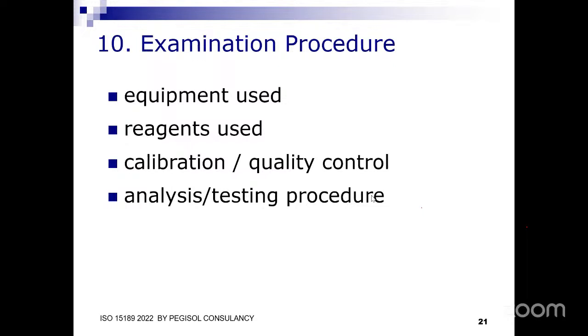So some people normally go for the unassayed QC because it's a little bit cheaper than the assayed QC. But whatever it is, if you look at the cost of everything, you have to run some samples before you determine the range of that QC. So that is also part of the cost you should look at. So that's the difference between assayed QC and unassayed QC. The assayed QC has a defined range, while for the unassayed QC you have to establish your own range. Okay, thank you.